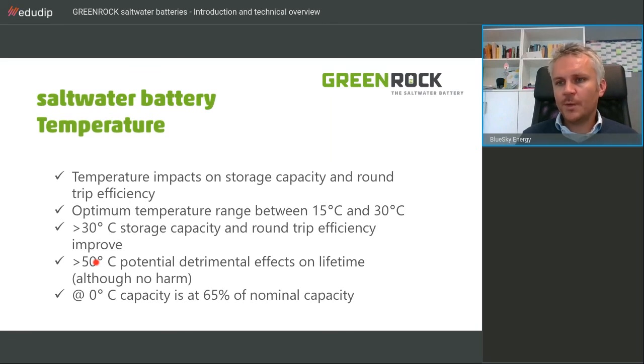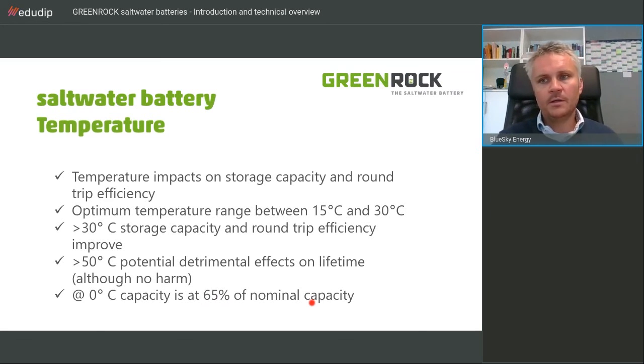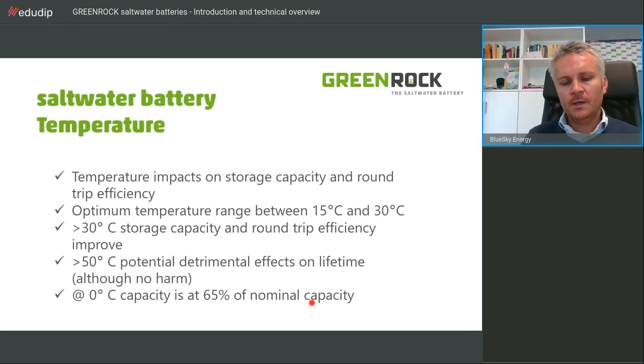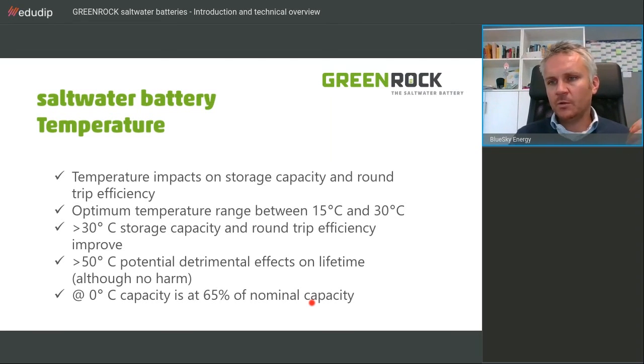if we go beyond 50 degrees centigrade, and therefore we spec it up to 50 degrees centigrade. And from a comparison perspective, when we have got 0 degrees centigrade, we are at 65% of nominal capacity, and that should be taken into account depending on where you are deploying your projects. And that is with our technology, but it also needs to be considered when you're benchmarking to other technologies. They have got the same situations, so that needs to be taken into account.